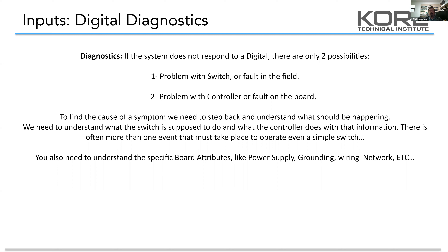With a digital input for a control system, there are really only two possibilities in a failure mode: there's either a problem with the switch or a problem in the field — the wiring — or the controller itself is unable to read its own output and consequently its own back input. With all of our inputs and outputs, you have to understand what the controller is actually asking the system to do. It's imperative that you know the sequence of operation for anything we're working on. There are several variables beyond just the circuit board that can prevent the control system from doing its job.